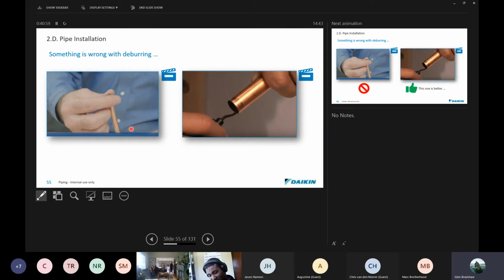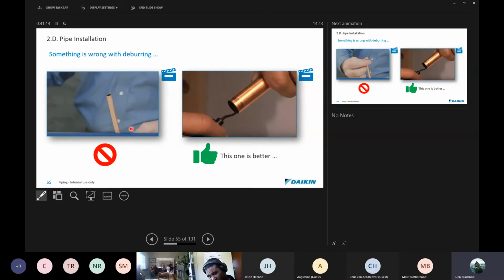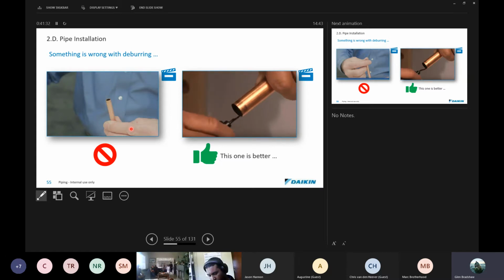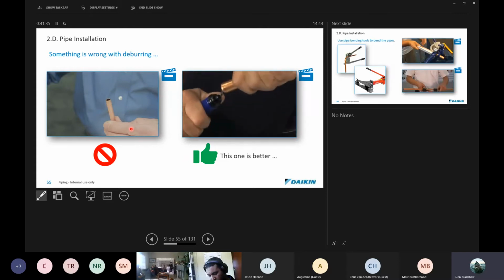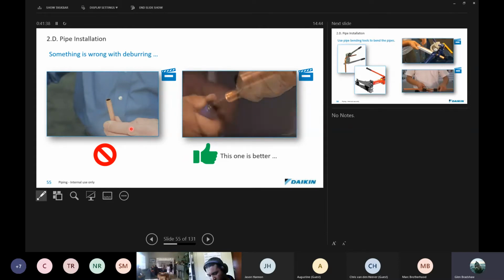All right. Also, when it comes to deburring pipes, there are some considerations that we must make. In the first video, you should not hold the piping up in the vertical plane when cleaning. All the material that you're deburring off is going to fall inside the pipes, and we don't want this traveling around in a refrigeration system. It's going to be deadly for compressors and other components. Hold the piping downwards, ensuring that any of the deburred material falls out of the piping.